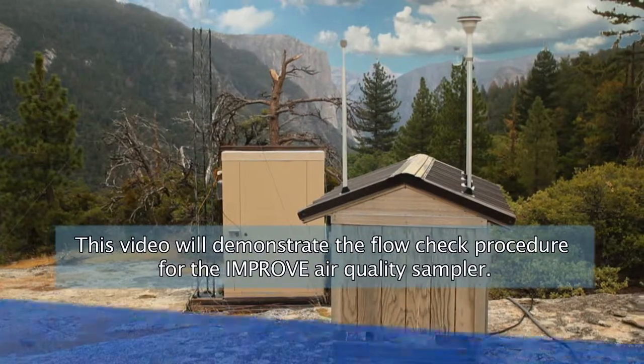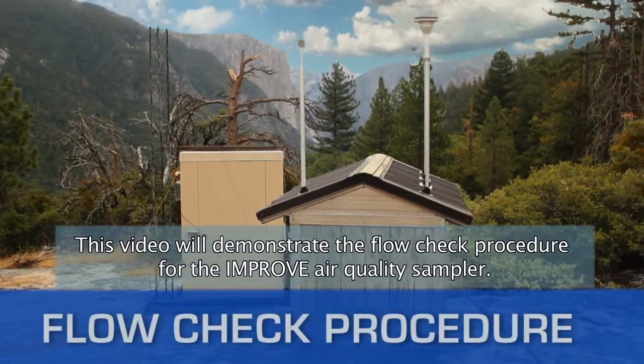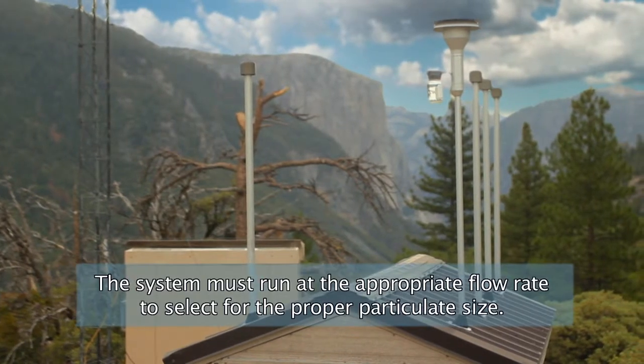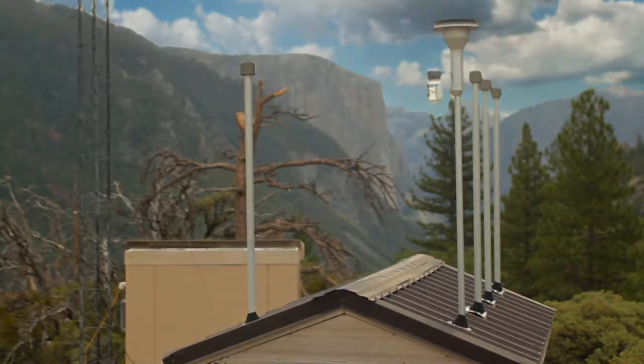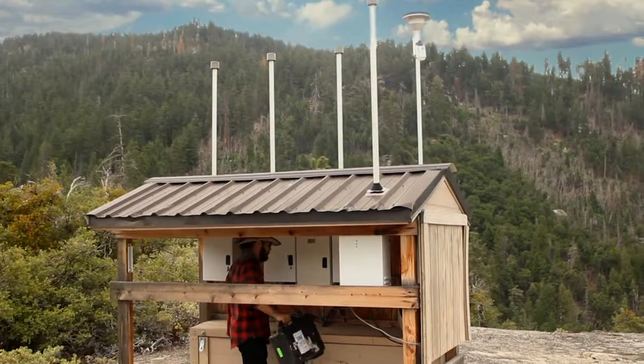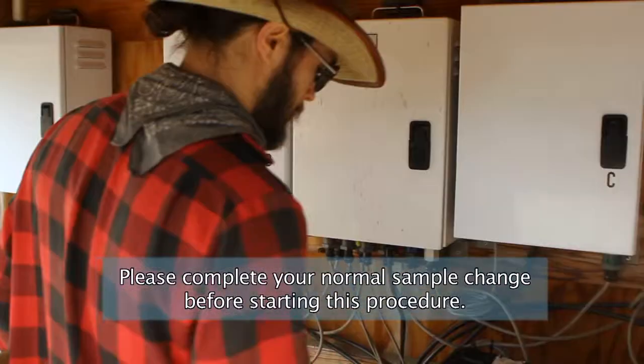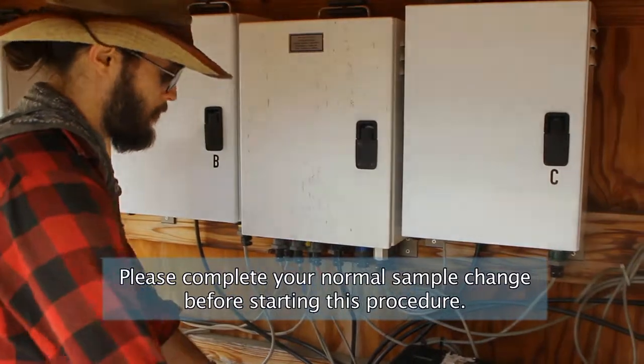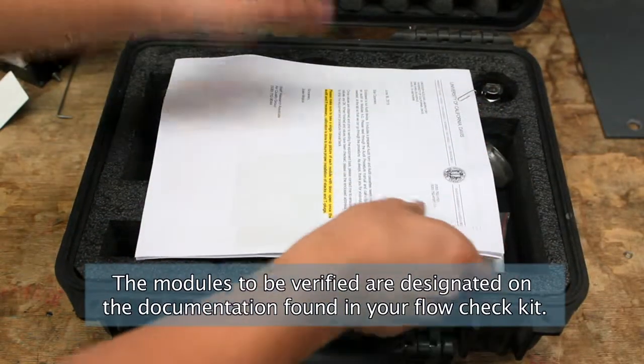This video will demonstrate the flow check procedure for the Improve Air Quality Sampler. The system must run at the appropriate flow rate to select for the proper particulate size. Please complete your normal sample change before starting this procedure. The modules to be verified are designated on the documentation found in your flow check kit.